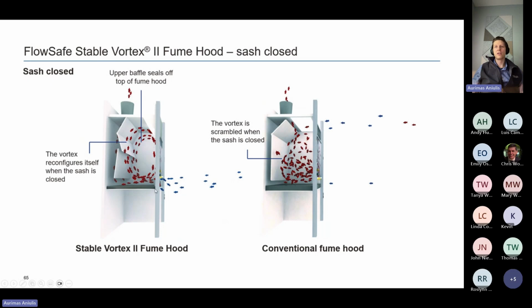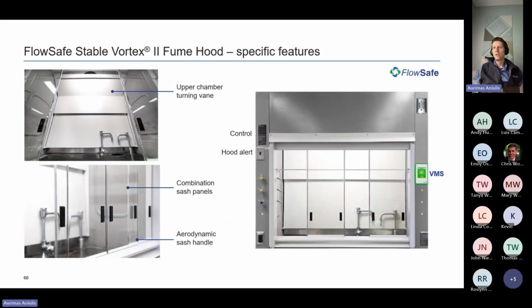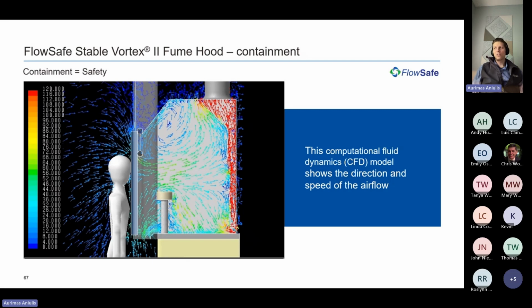Conventional fume hoods were about 100 feet per minute. The Stable Vortex 2 fume hood passed the ASHRAE 110 containment test at around 53 feet per minute. We don't recommend that. We say the lowest you should go is about 60 feet per minute. These are our dynamic baffles inside of the workspace. We have a combination sash that's both horizontal and vertical sash panes. It comes with a vortex management system display for all your alarm and set point conditions. This is our sensor that we use for sidewall sensing of that vortex. And lastly, a lot of this is not only CFD verified, it's tested and verified through the ASHRAE 110 testing. Again, I can't stress enough how important the ASHRAE 110 test is for fume hood safety determination.